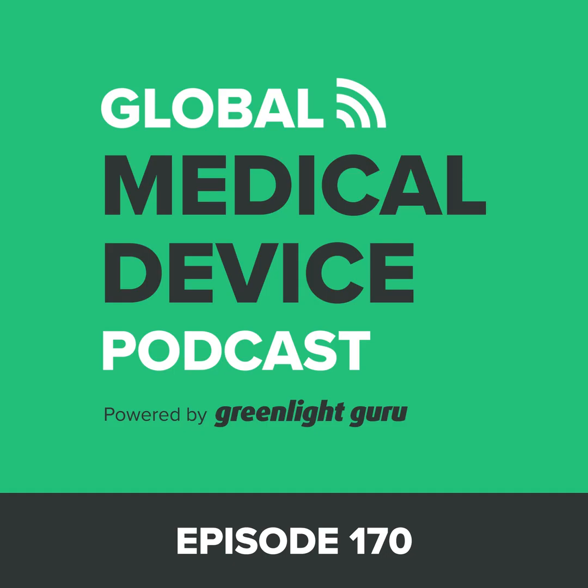And so, some of these things that you can start to put together, one of the ways that you can get a hint of what FDA is looking for is they have published online a pretty detailed guidance about what software devices need to provide to FDA for a market submission. So this would be a 510(k) or a de novo. And they have a whole list of documents, with quite a bit of detail involved in describing each one of them.